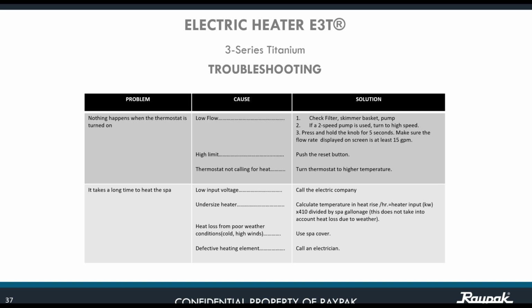If this is a sand filter, fine. If you have a cartridge filter, make sure that you remember when was the last time you serviced the cartridge. Maybe you need to replace the cartridge. Also, check the pump. Check that the impeller does not have any debris, especially here in California. I heard that sometimes when there is a pine tree, those small things start to go into the pool and get trapped on the impellers. So that is going to prevent the pump from delivering the proper flow to the filter, and therefore to the unit.